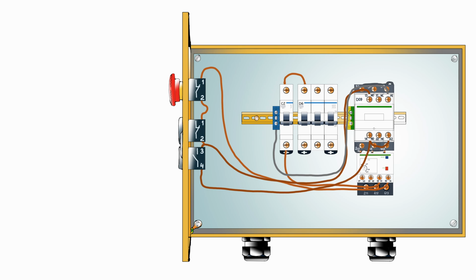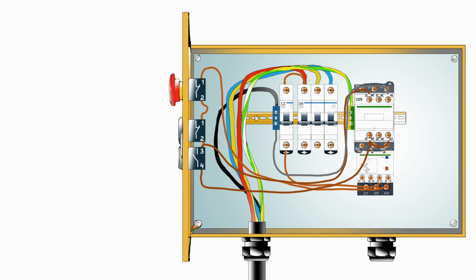And then on the power circuit side, it's pretty straightforward. All the power circuit components are connected in series with our electric motor, and it shouldn't be a difficult thing for this non-reversing direct online starter. So we just connect our supply to the top of our circuit breaker, and then from the bottom of our power circuit breaker, we'll take our 3 conductors and connect them to the top of our switching contactor.